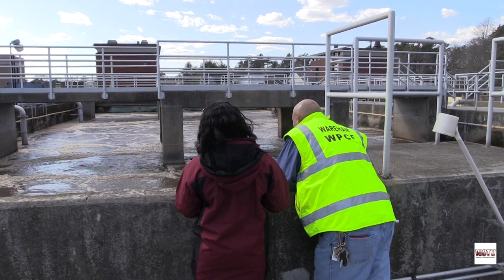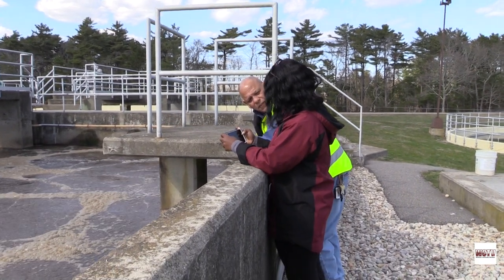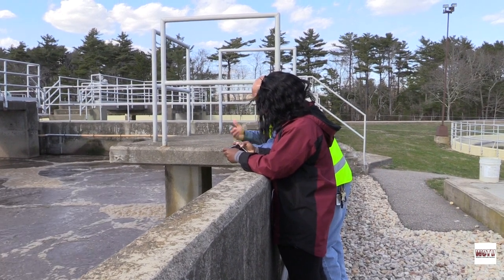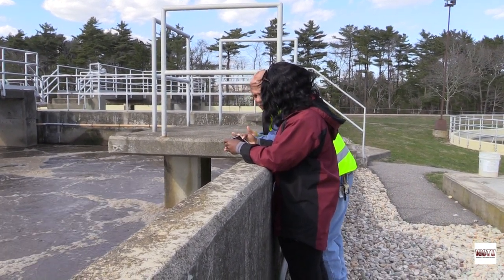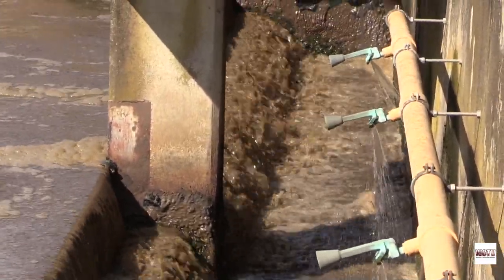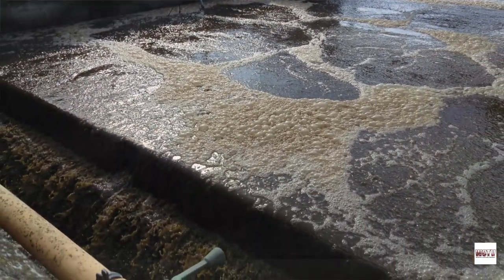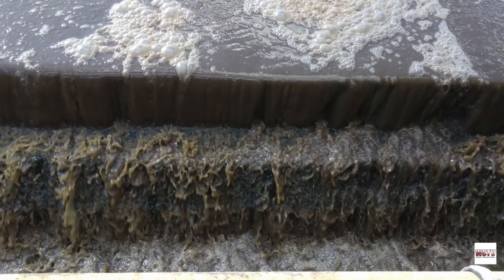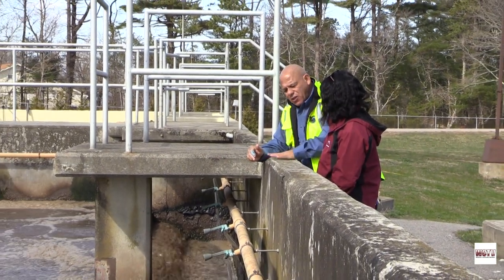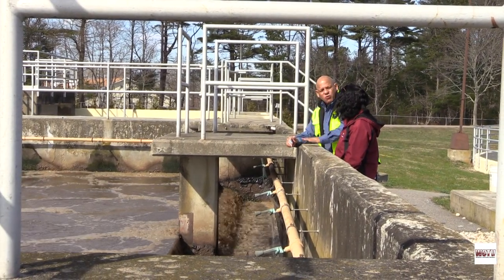So this is what we call the secondary treatment. We're into secondary treatment, and this is called the extended aeration. Because we talked earlier, we keep recycling and we aerate it, so it's an extended period of time, 10 days. And they can eat a little less, a little more, depending on the time of the year. As it gets warmer, it's harder to get DO saturated because of heat and water, it's a chemistry thing. So George may keep it a little bit longer. He has to figure that out. Again, it's a daily sliding thing. Every day, the testing and lab. George gets in here at 7:30 in the morning, and when he leaves at 4, it's nonstop because he's got to constantly make sure that this system is working properly.